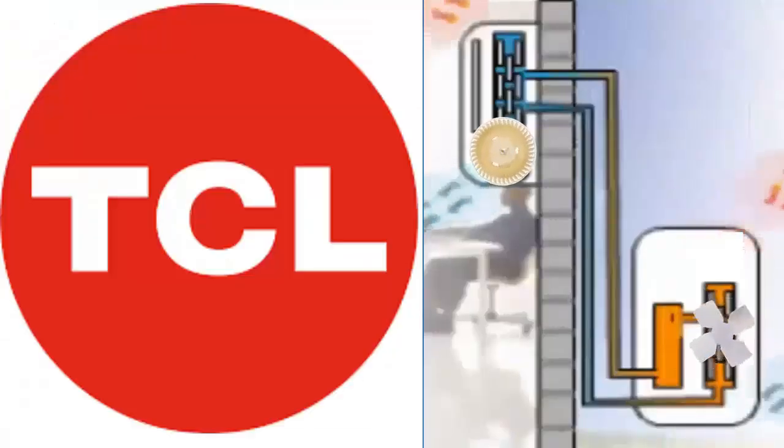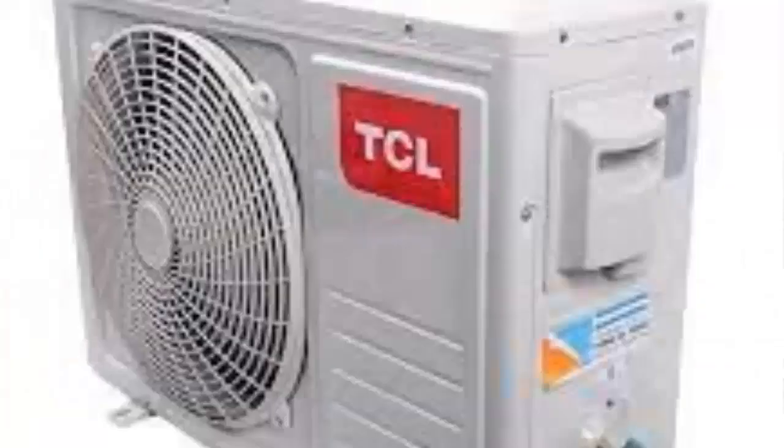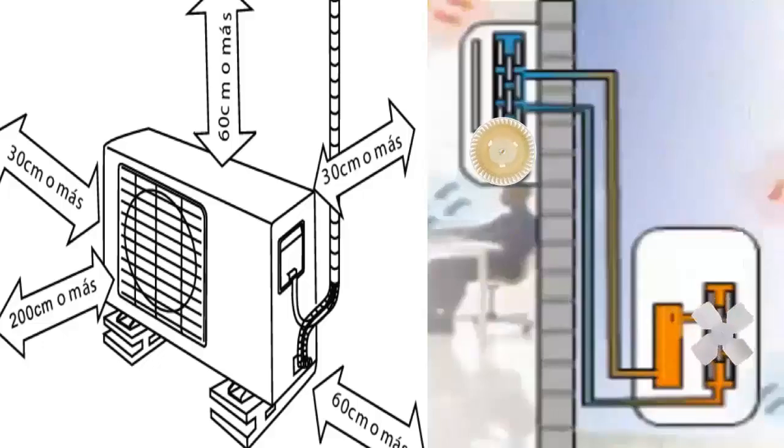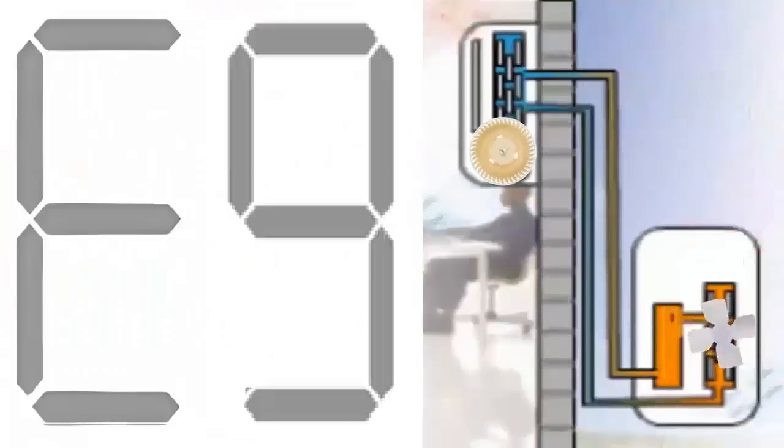Step 4: Additionally, perform a visual inspection of the outdoor unit. Check for cleanliness, proper airflow, and correct fan operation. If the problem is poor heat exchange in the outdoor unit, the E9 error code may take a few minutes to manifest and often does not trigger immediately.